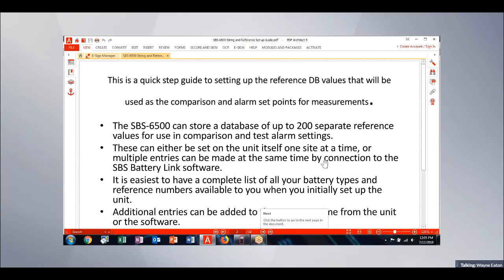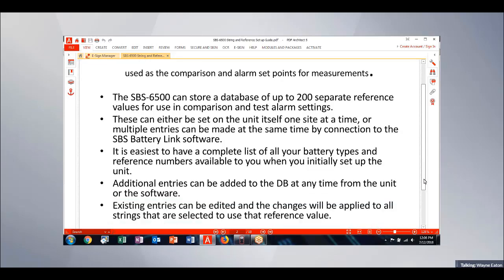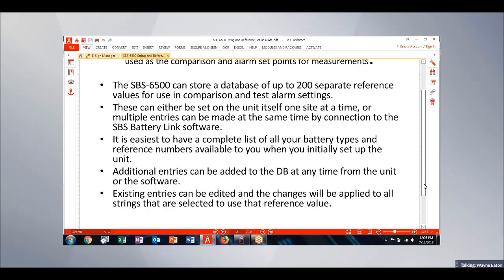So if I had a battery installed in a substation, and let's say I didn't know what its reference values were at the time that I went out and took the first set of measurements on it, I can go back and put the correct reference values in at a later date and time, and it'll update all the results that have been taken up to that point. I can make additional entries into that database or into that string list at any time. So from the software or from the unit, if I put in a new set of batteries, I can add that set of batteries to the unit without having to delete anything or start over again. And then those existing entries can be edited, and those changes are applied to all the strings that use those same reference values.